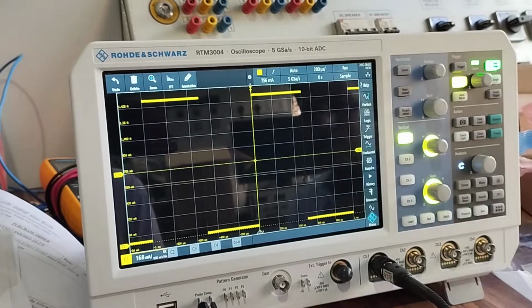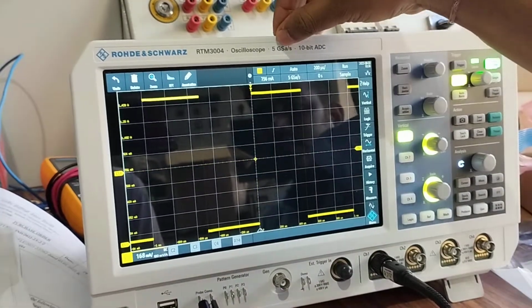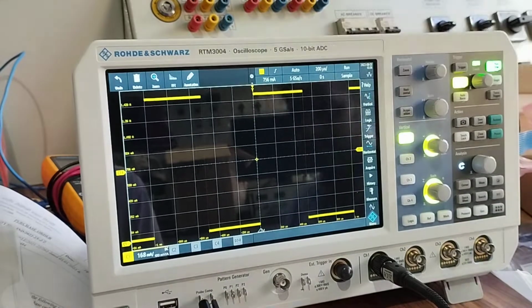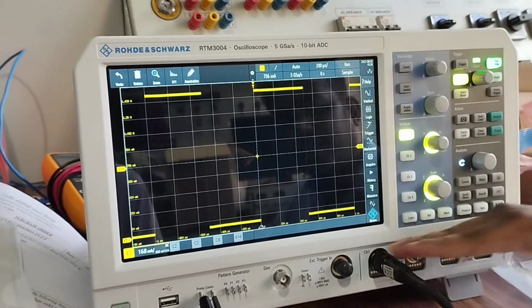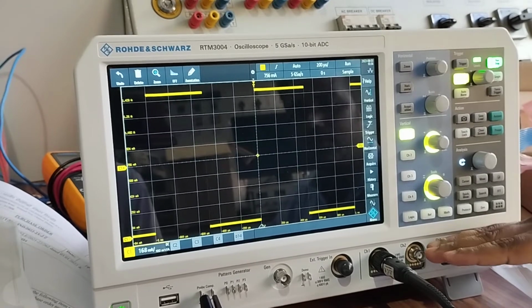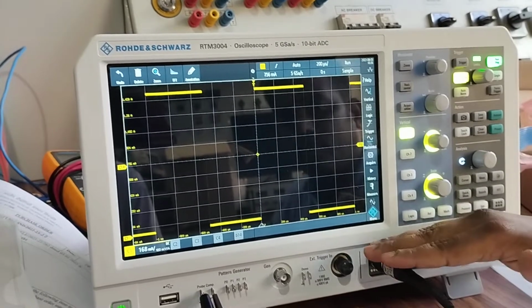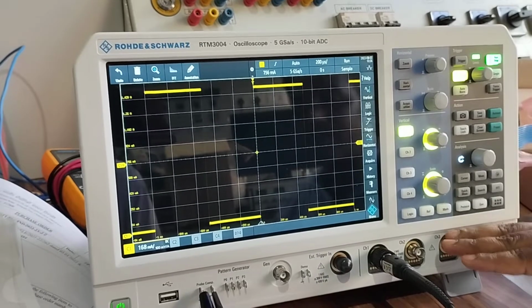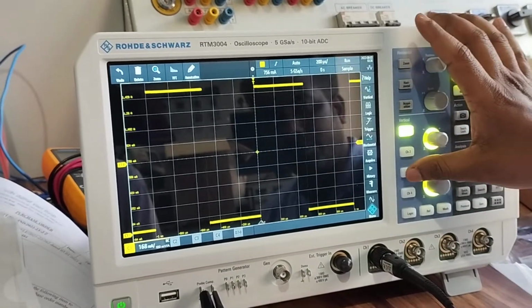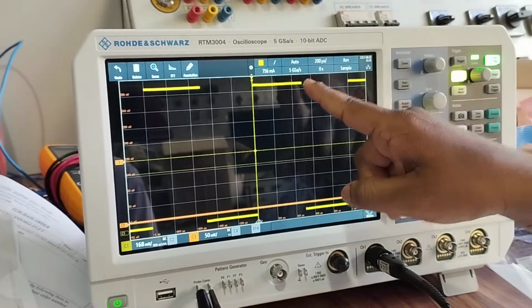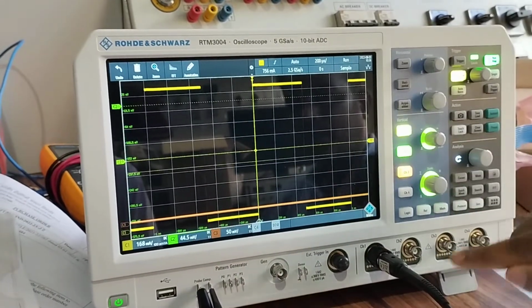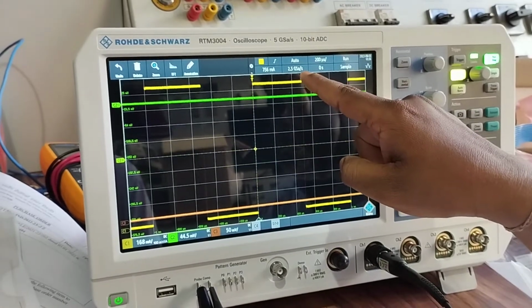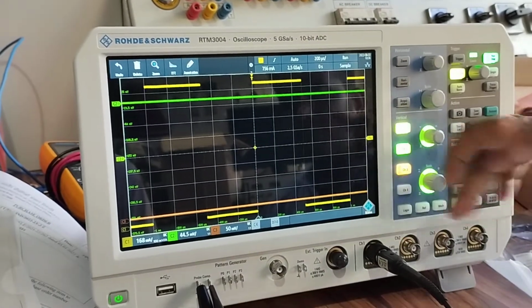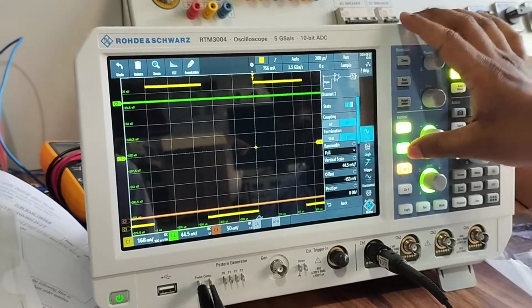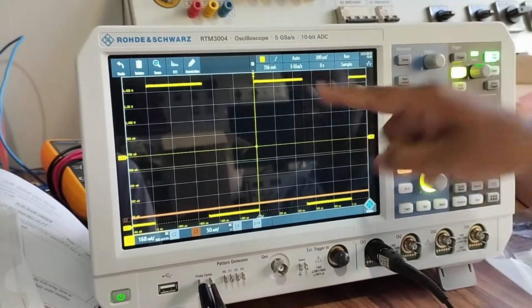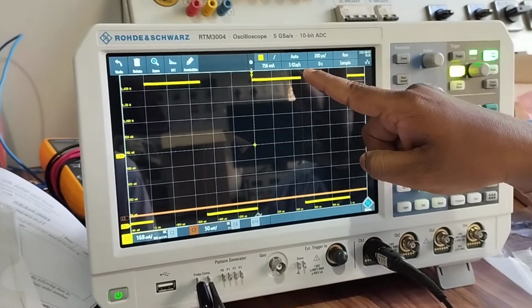And I just want to confirm one more thing. Here, if you see, it is mentioned 5 giga samples. On all channels it is 2.5 giga sample sampling rate. If you use only channels 1 and 3, the sampling rate will be 5 giga samples. If you use 1 and 2, by default it will fall down to 2.5 giga samples, like we have the interleaving between 1 and 3 and 2 and 4. So that is how you see. Now again I have switched off the second channel, and it has become 5 giga samples.